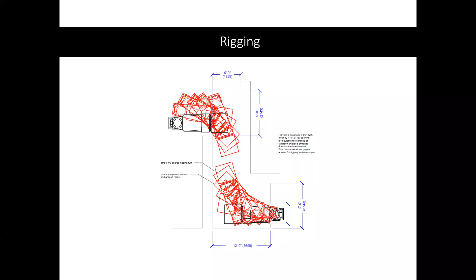This is just to show you an example of a rigging design. There's a typical rigging design of a linear accelerator, which is provided by the vendors. So this should be obtained from the vendor prior to the construction. We should know the dimensions of the equipment. We should not end up with bunkers, and our shielding calculations should not end up with bunkers, like that, where we cannot house the equipment once it arrives.